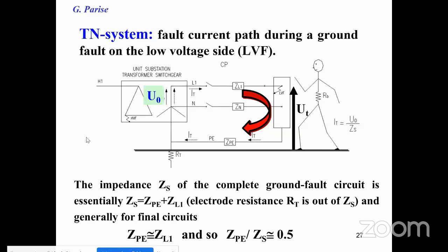And we generally, in the IEC approach, consider in the terminal circuit that the impedance of the line and the impedance of the protective conductor have to be dimensioned in the same way. So we can consider that the impedance of the complete circuit is equal to the sum of the impedance of the line and the impedance of the protective conductor. Considering that they are equal, the impedance of the protective conductor is half the value of the complete impedance of the fault.